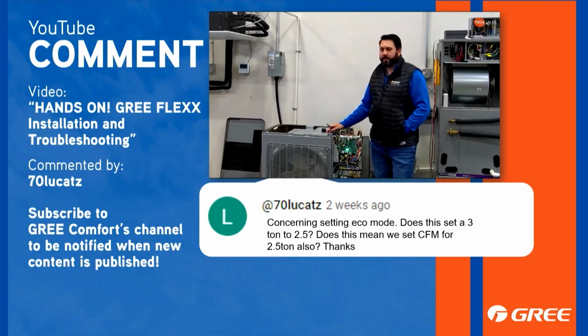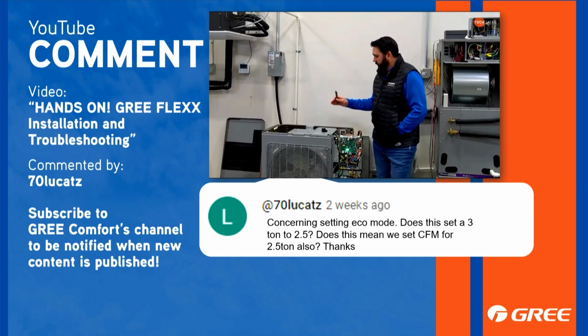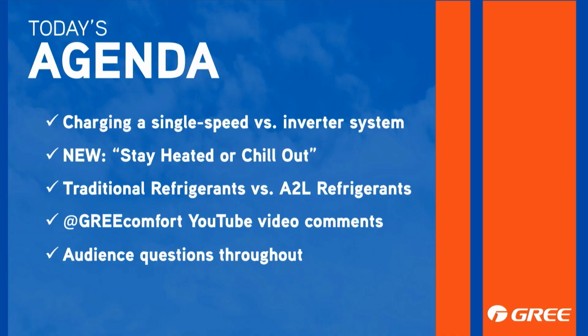I remember being out there with a garden hose trying to get that compressor to cool off, and beating on it with a hammer to see if I could get that overload to go back in, so that I could put refrigerant back in it. Or maybe it's because the coil was dirty or the filters were, they change them every month, right? You always check the trash can and you can see that filter they changed, right? Every month, right? Before you get called out. So maybe it doesn't have an overload at all, like the FLEXX. The FLEXX doesn't have an overload. The inverter board is the overload.